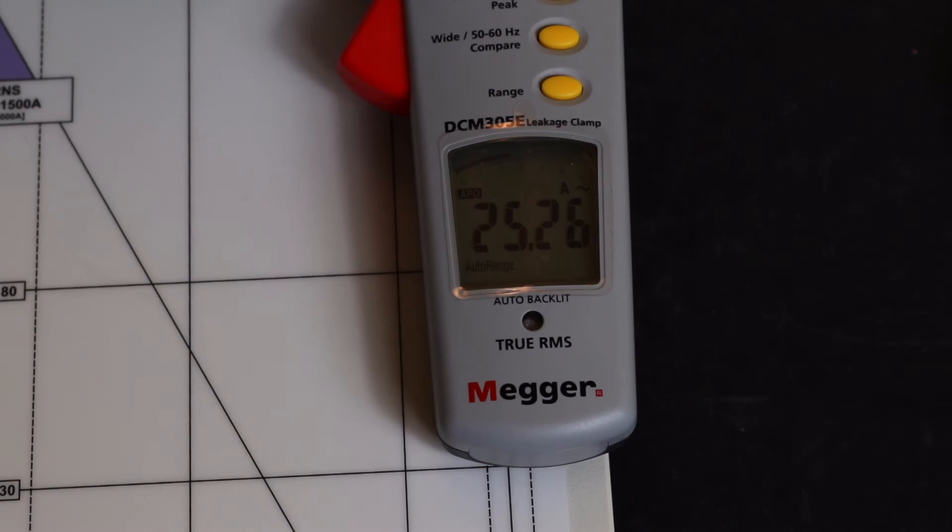Okay so we'll go up to 5 amps it should give me 50 amps. We've got 49.94 and then we'll go up to the full 10 amps should give me 100 amps and we've got smack on 98.9.